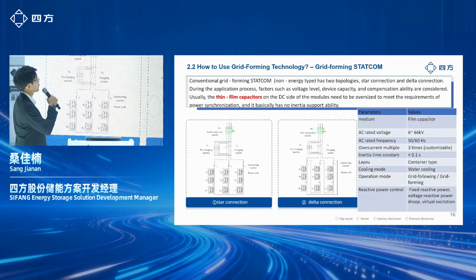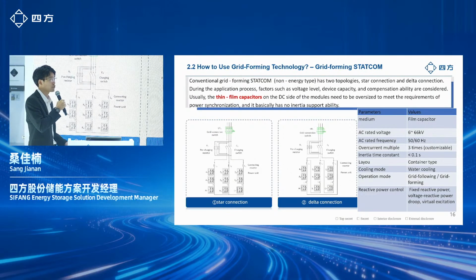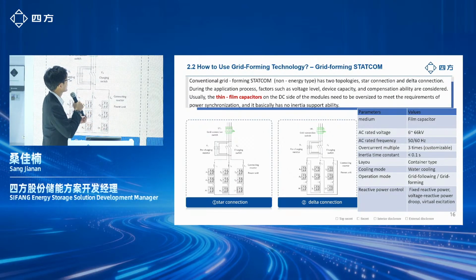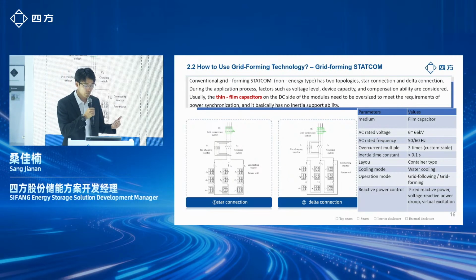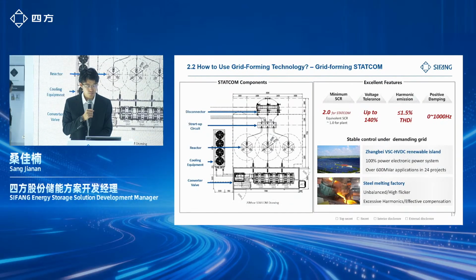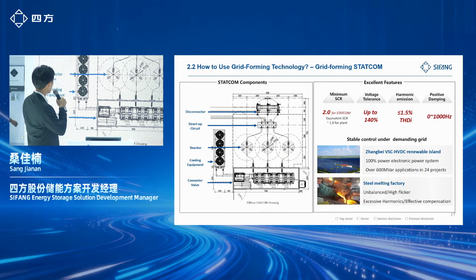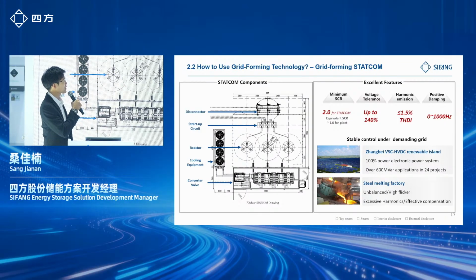Okay, here is the first product, Grid-Forming STATCOM. This is the traditional one. We all know that the conventional Grid-Forming STATCOM with non-energy type has two topologies: star connection, right, and delta connection. On the DC side, it adopts thin film capacitors. If you need 300% overload, we will oversize the capacitors on the DC side. It can also be custom sized to adopt the AC rated voltage from 6 kV to 66 kV, with a liquid cooling system. Here is a layout, including the reactor, cooling system, valve, disconnector, etc. Usually, a Grid-Forming STATCOM is used in scenarios like a steel melting factory or some renewable island.